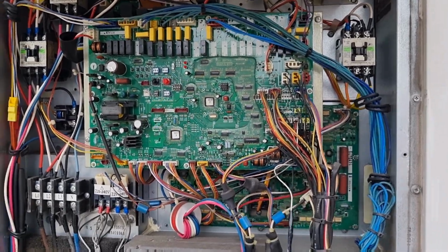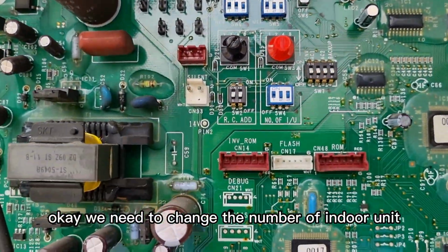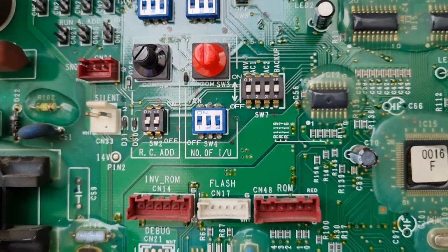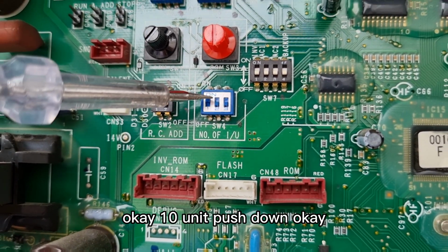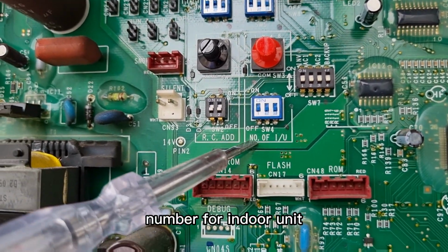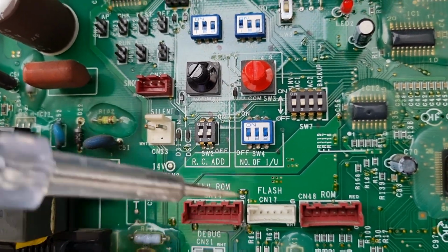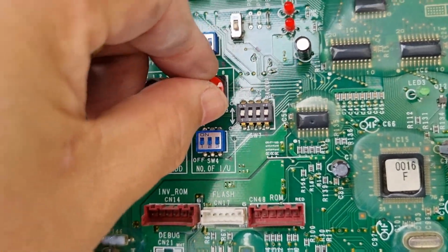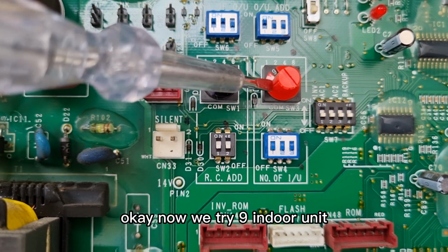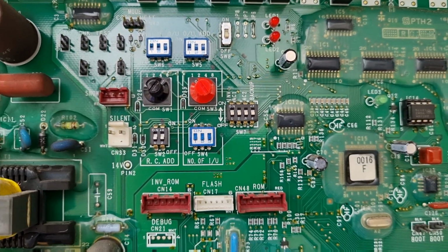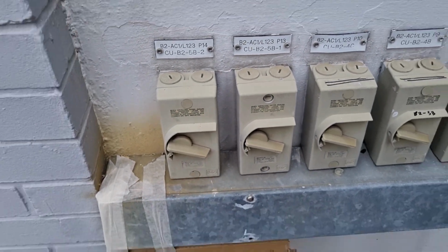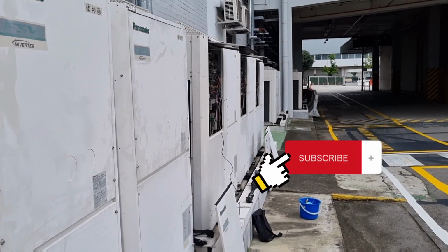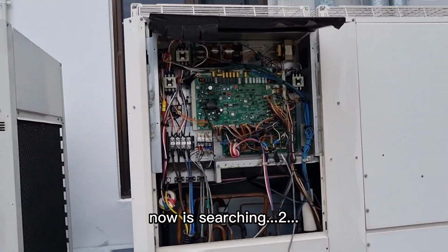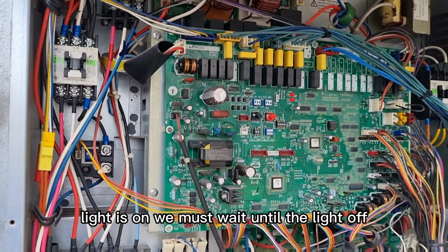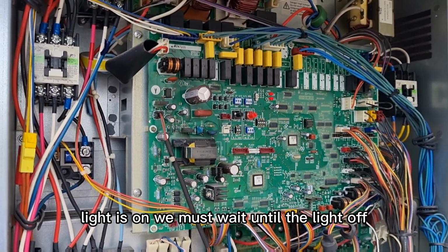Okay, power light is off. Okay, we need to change the number of indoor units from 10 units to 9 units. Okay, 10 unit, push down. Okay, number of indoor units, 10 unit, push down, off. Okay, 0, we set to 9. Okay, now we try 9 indoor units. Okay, now searching, two lights are on. We must wait until the light is off.